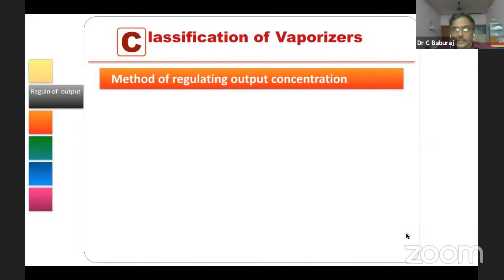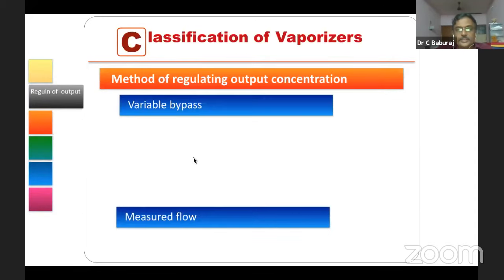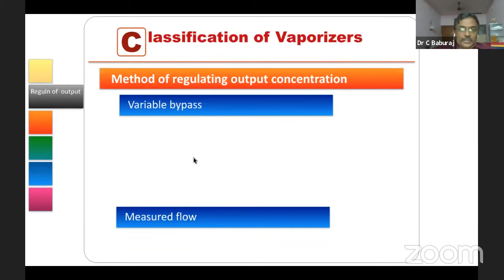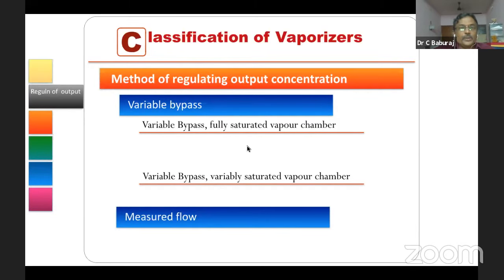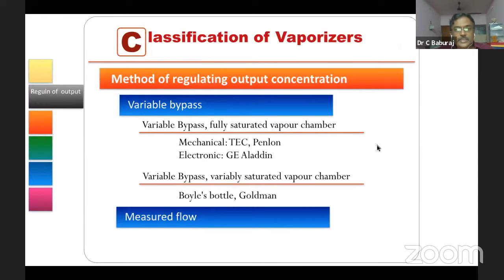The second classification is by method of regulating output concentration. There are two divisions: variable bypass and measured flow. Most modern vaporizers excluding a few are variable bypass. A classical example of measured flow is the copper kettle. Variable bypass can be further divided into variable bypass with fully saturated vapor chamber — our Tec vaporizers come here — and variable bypass with variably saturated chamber, example being Boyle's bottle. Measured flow example is copper kettle.